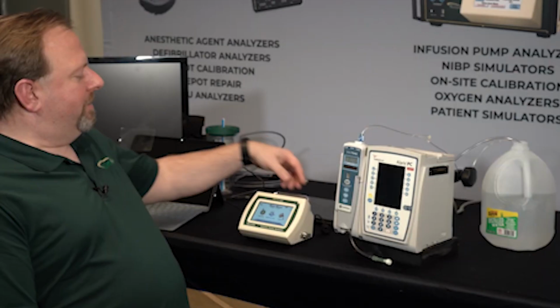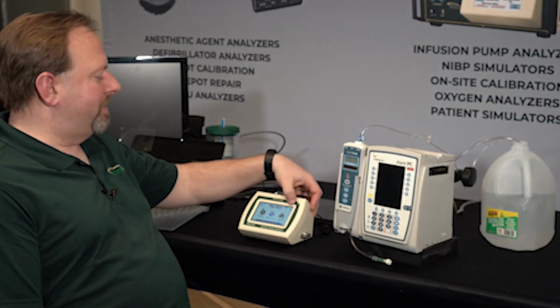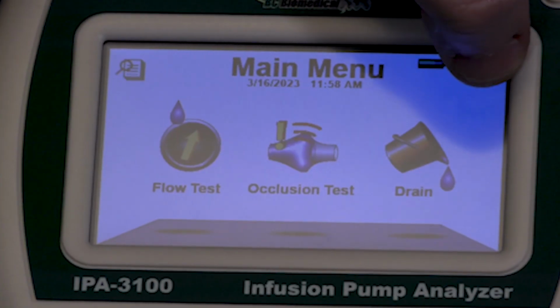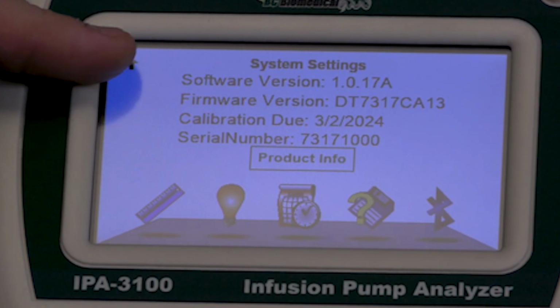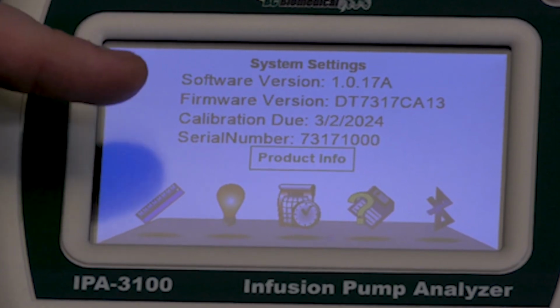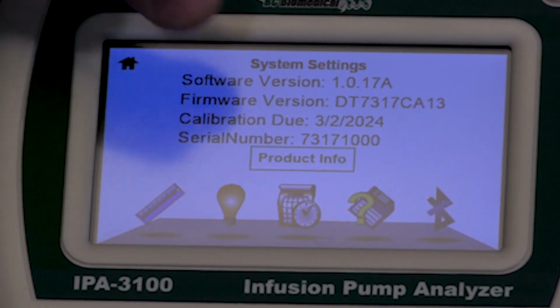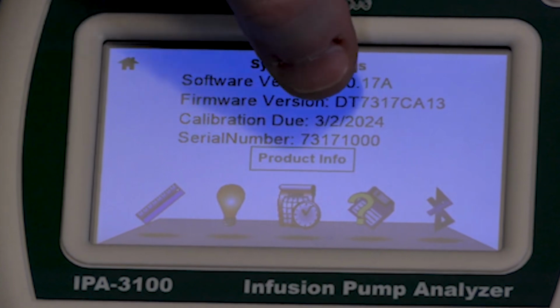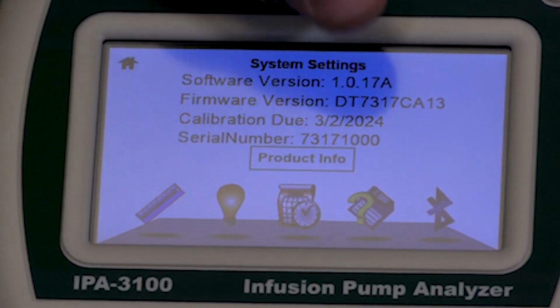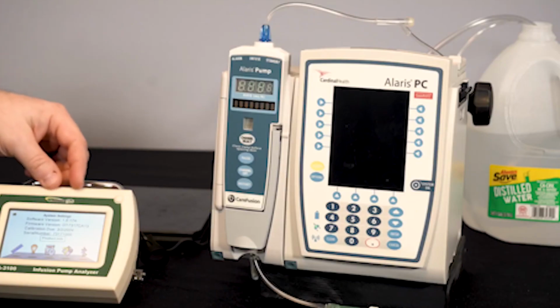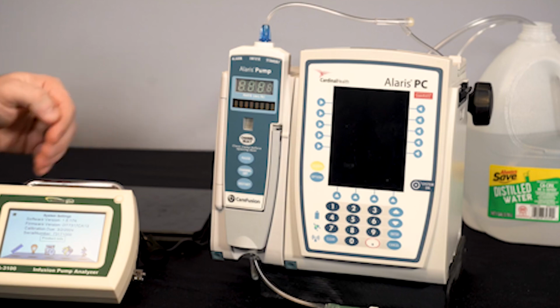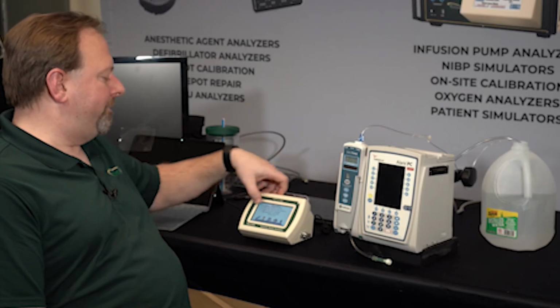In this segment, we're going to overview all of the features and set up configurations for the IPA-3100. To view the system settings from the main screen, we press the gear button at the top right. That shows us the software version, firmware version, and calibration due date. Now this one's important because as we get closer to our calibration due date, there'll be a notice on the main screen saying that your calibration is due soon or your calibration is past due.